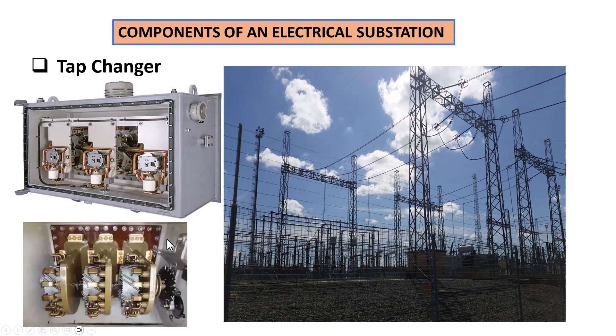So what exactly is a tap changer? The tap changer is basically a device that's used with a power transformer. Its main role is to regulate the voltage ratio on the secondary, regardless of what is happening in the primary. So we may have primary voltage variations, but the tap changer will ensure that the secondary voltage has some regulation — there is no fluctuation.